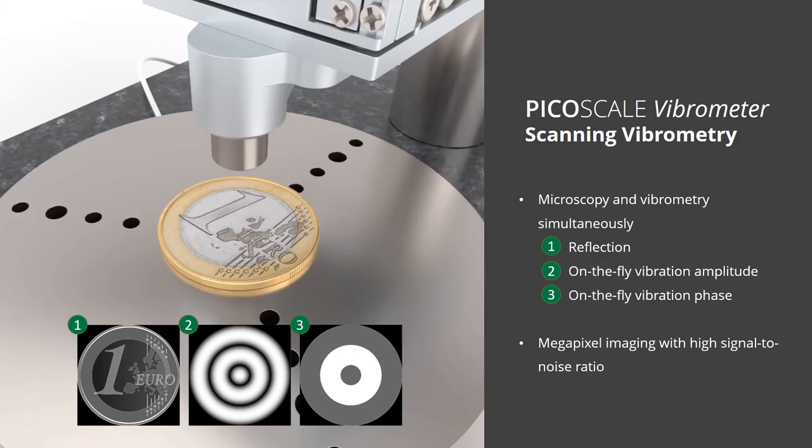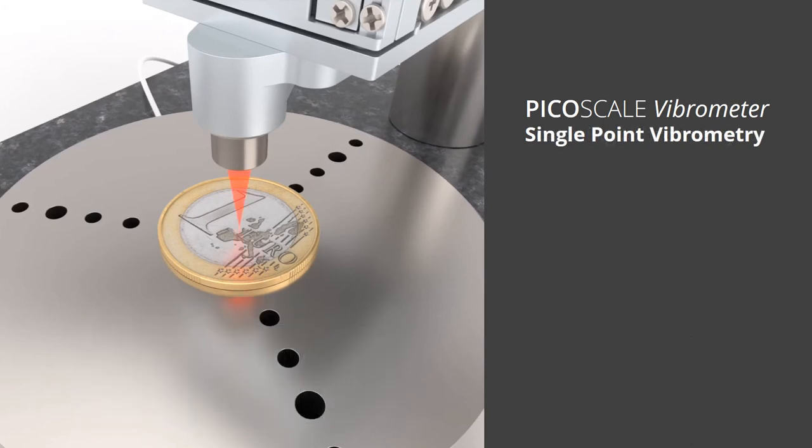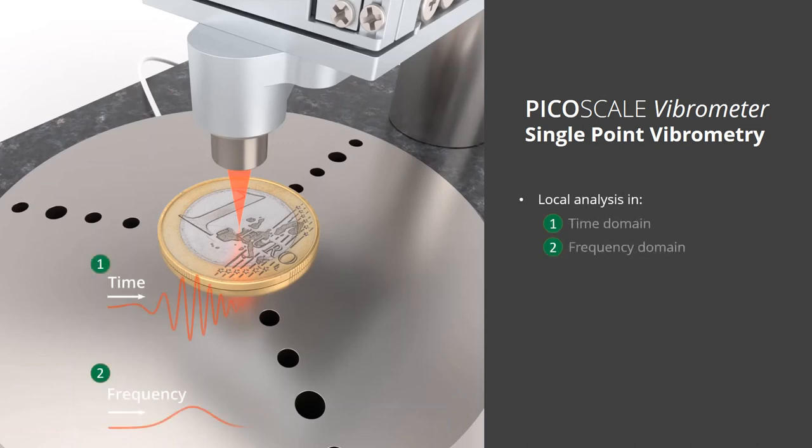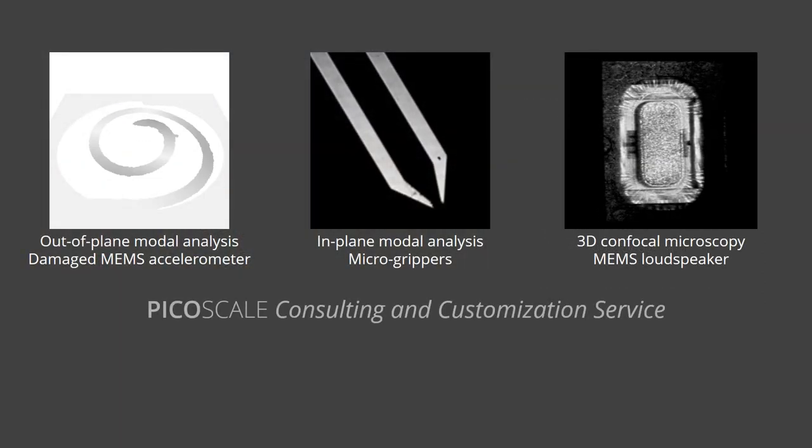SmarAct PicoScale Vibrometer can also be used to resolve motion at individual points in both time and frequency domain. With a noise level below one picometer and a sub-hertz spectral resolution, there is almost no limit to the type of structures that can be investigated.